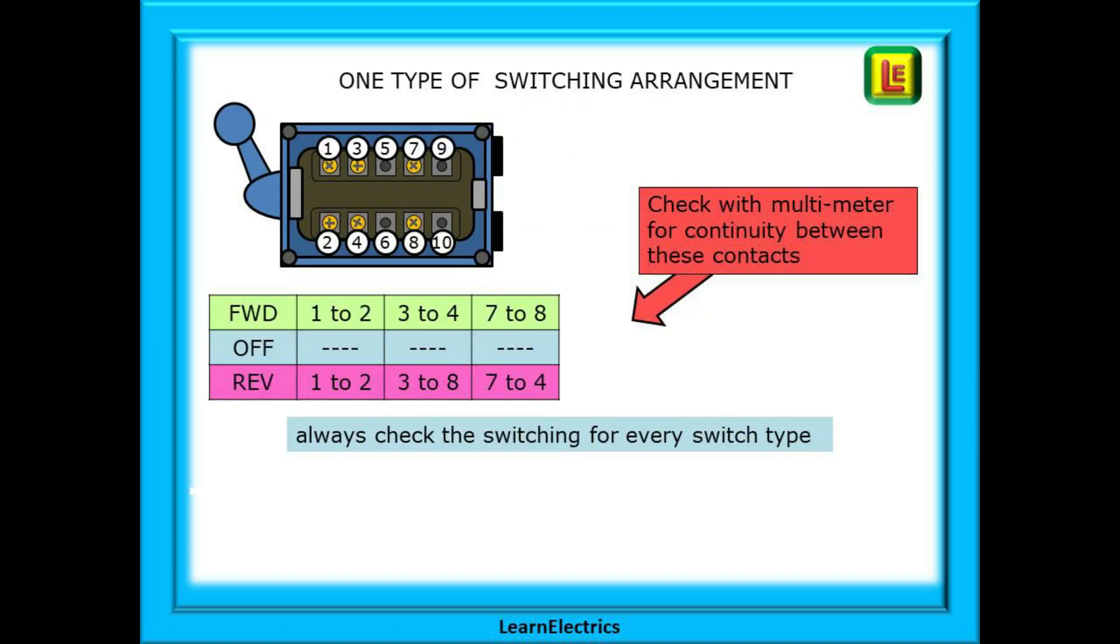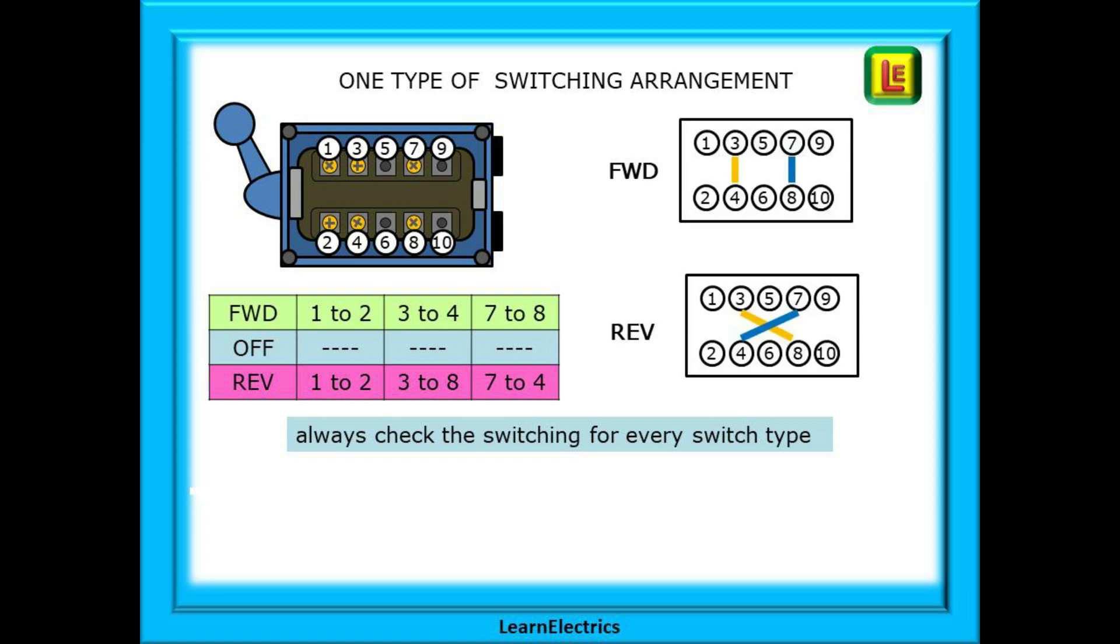Looking at these contacts we can see that in the forward direction we have a straight through arrangement: one to two, three to four and seven to eight. In a reverse direction one still goes to two but the other four will cross over, three to eight and seven to four. And in the off position nothing is connected to anything else. Always check your own switch contact arrangements.